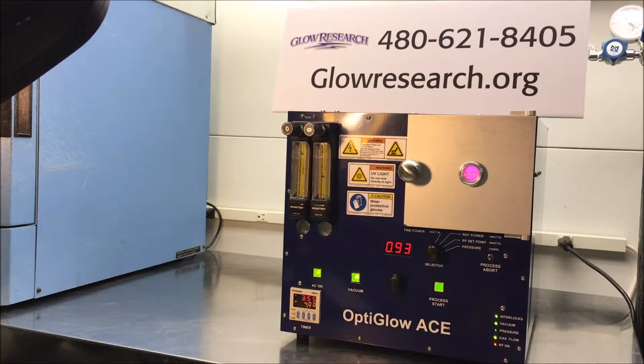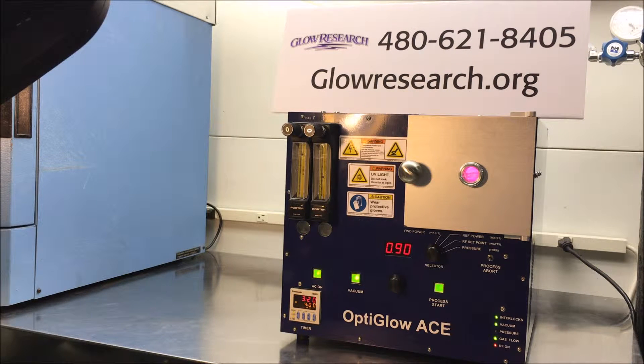Hello, today we are going to talk about the Glow Research OptiGlow ACE plasma system and the operation of the system. The system is designed for up to four inch wafers and can handle various different types of substrates. The OptiGlow ACE system is used primarily in FA labs for ashing, cleaning, plasma activation, plasma cleaning, pre-bonding applications, PDMS, etching polyimide, and parylene. We also have etched oxides and nitrides to remove different types of protective coverings on ICs like packages and opening up packages.